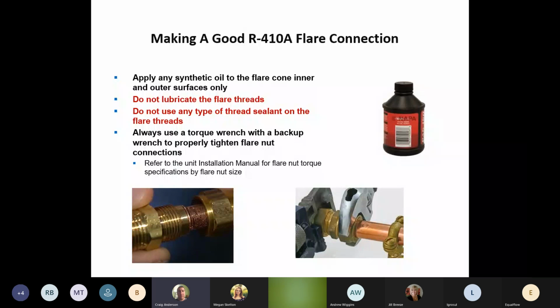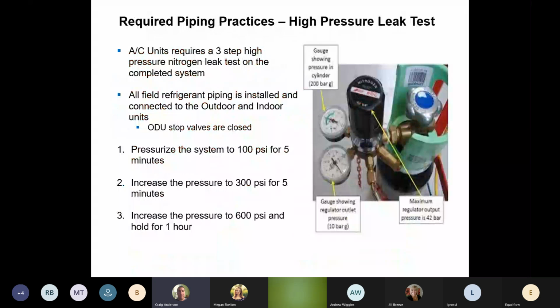Pressure checking, another big thing out there. We call it the 3-step. All the 3-step is doing is saving you nitrogen. Let's not put 600 pounds in it and see if we've got a leak. If you've got a leak, you just lost that 600 pounds. Start off with 100 PSI for about 5 minutes. If it doesn't move, bump it up to 300. Doesn't move, bump it up again. This way, if we do have a leak, you're not losing as much nitrogen. It's not doing anything else but saving you some nitrogen down the road.